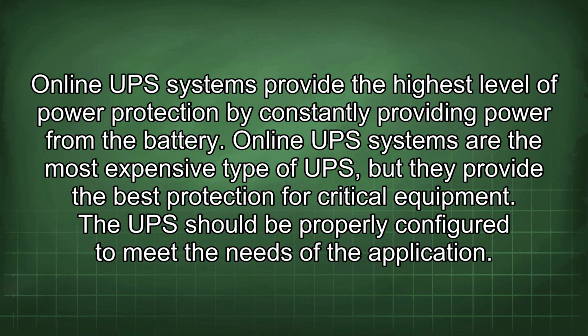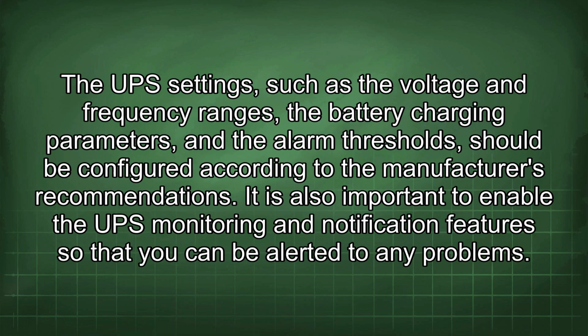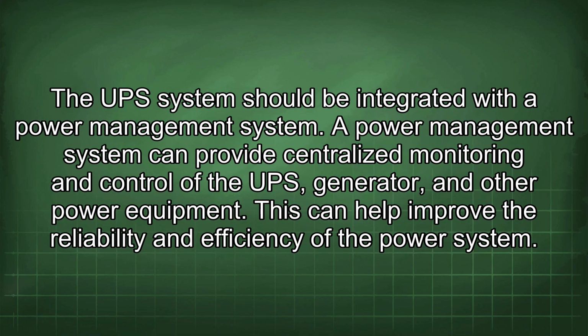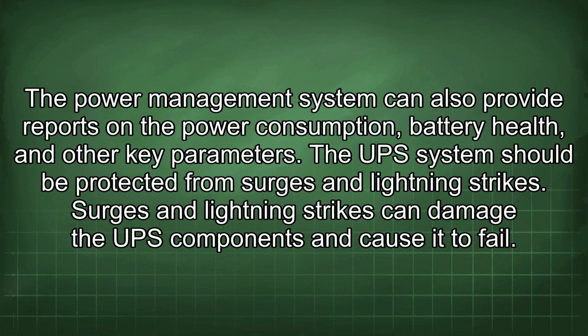The UPS should be properly configured to meet the needs of the application. The UPS settings such as the voltage and frequency ranges, the battery charging parameters, and the alarm thresholds should be configured according to the manufacturer's recommendations. It is also important to enable the UPS monitoring and notification features so that you can be alerted to any problems. The UPS system should be integrated with a power management system. A power management system can provide centralized monitoring and control of the UPS, generator, and other power equipment. This can help improve the reliability and efficiency of the power system. The power management system can also provide reports on the power consumption, battery health, and other key parameters.